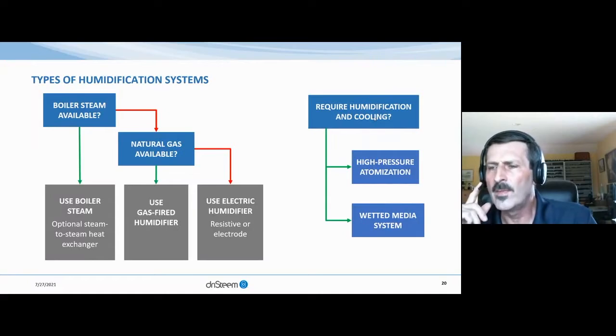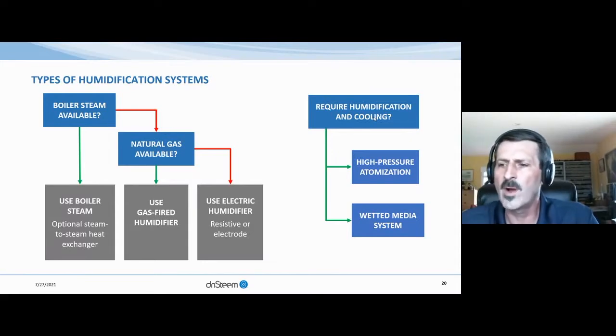If higher accuracies are required, then a high-pressure atomization system may be your first choice. HPA systems are capable of multi-zone control and can be used in fairly small spaces, as well as with ceiling heights as low as 10 feet. In addition, high-pressure atomization systems can operate on your process water, either reverse osmosis, RO, or DI, deionized water, or ultra-pure water. If more general levels of humidity are required, and space is available in duct or in the air handler, a wetted media system may be appropriate. Remember also that systems can be mixed and matched, where lower accuracy and higher capacity centralized systems can be married with a local or zonal high accuracy unit that can be trimmed to meet the required process requirements.